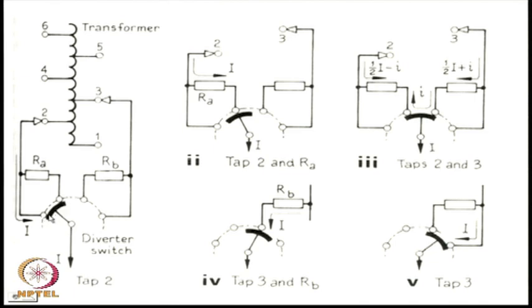While it is supplying from tap 2, this is the position of the switch. This resistance is shunted by this short circuit, so current actually flows through this path and not through this resistance. The first step in tap changing is to move this switch from this position to this, so that the external connection is now removed from tap 2, still connected to tap 2, but now through this resistance R A.